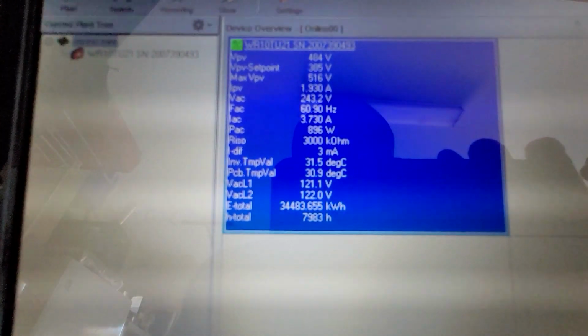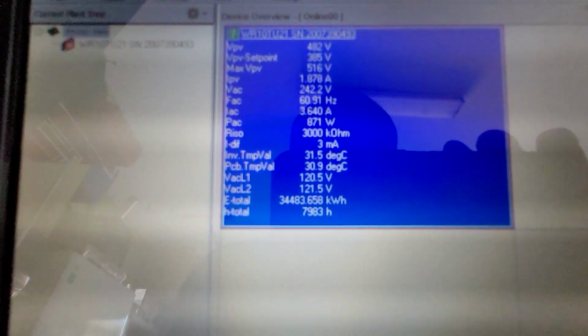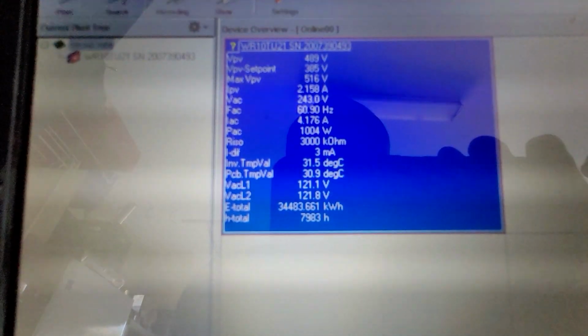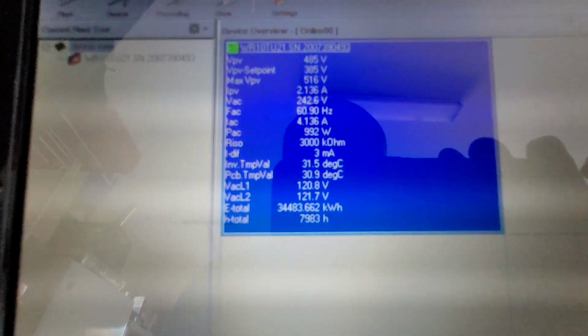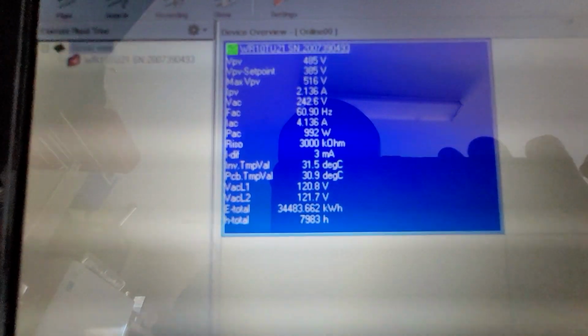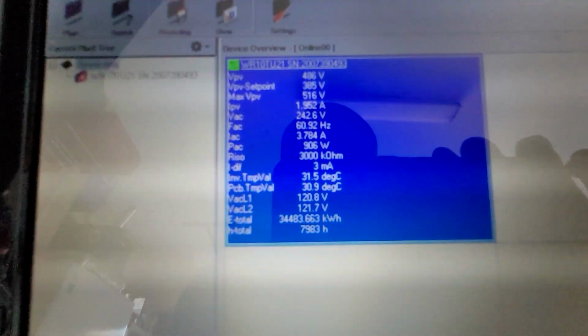for this home. It's just got a few things on inside, which is the best time to figure this out, because you want the lowest load, because that is the hardest time to get the inverter to throttle. So that it doesn't trip off, because what we're doing right now is we're throttling the inverter to just barely meet the load so it doesn't trip off and seesaw back and forth of charging and then discharging.